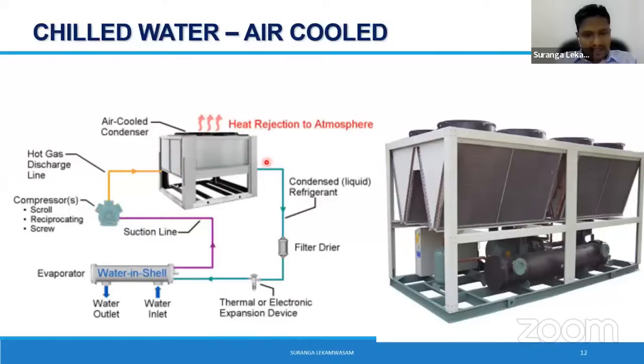If I simply explain, you can see the compressor here. You have the air-cooled condenser. Then you have the expansion device. Finally, you have a shell and tube heat exchanger. You can see now this evaporator cools not air like previously. It cools water, and you produce chill water and circulate that chill water throughout the building through your piping network. And there at the end, you have to install your end equipment like fan coils or air handlers. Then they will do the cooling of air as per your requirement. So that's how air-cooled chillers work.